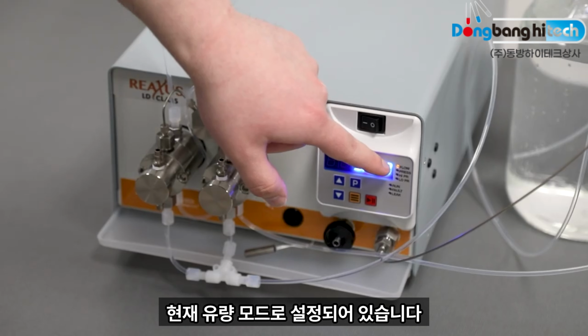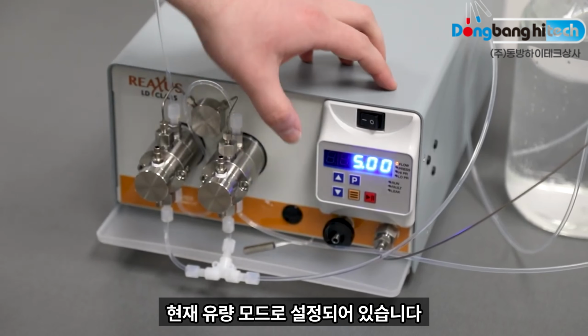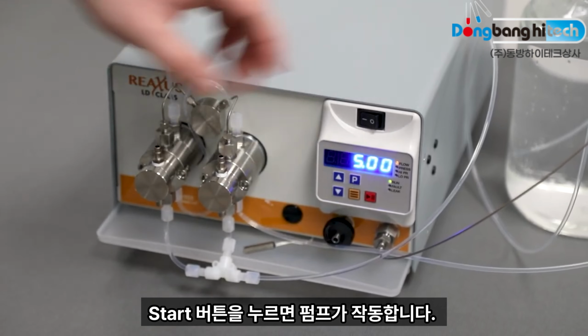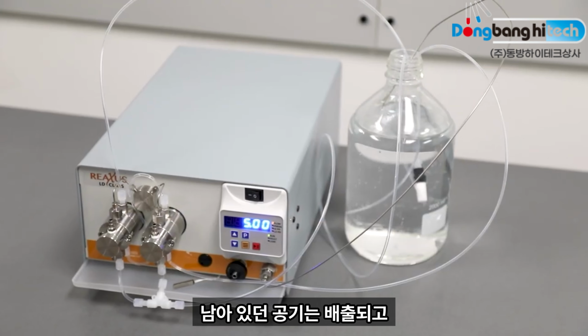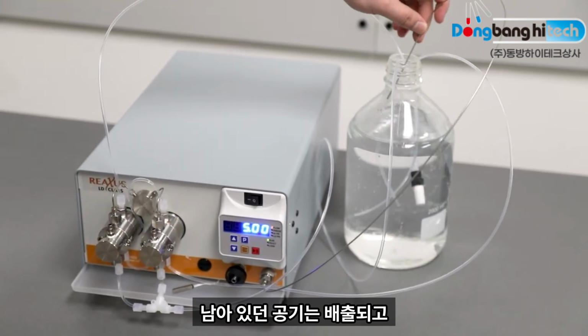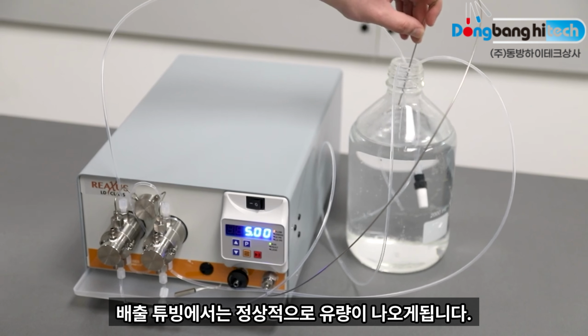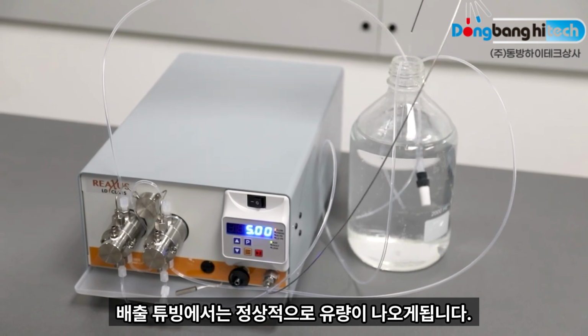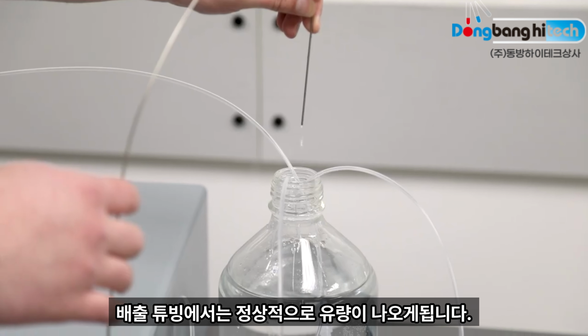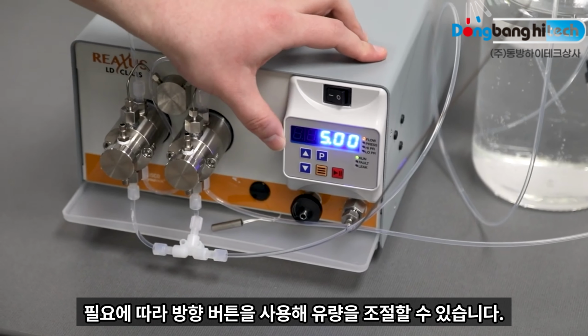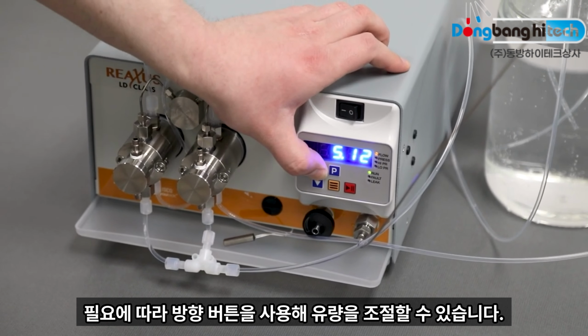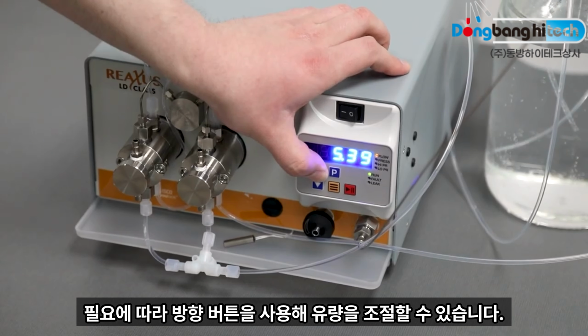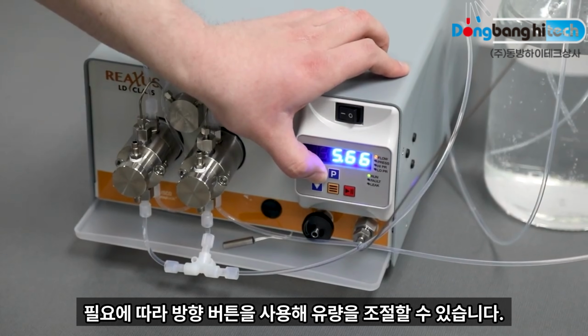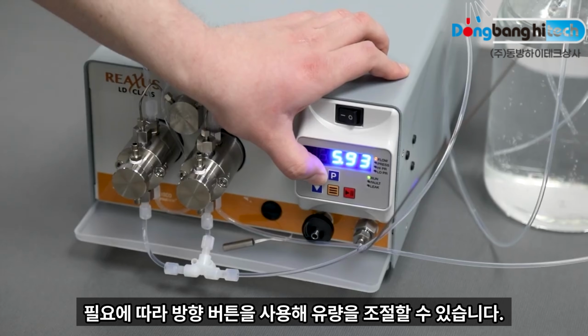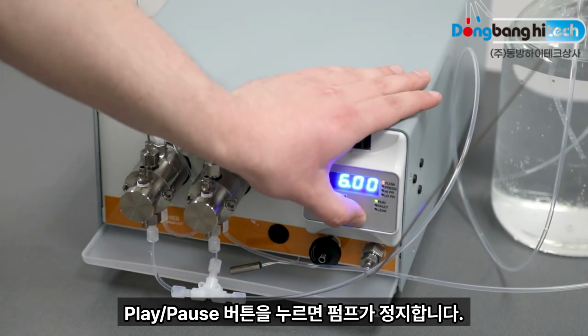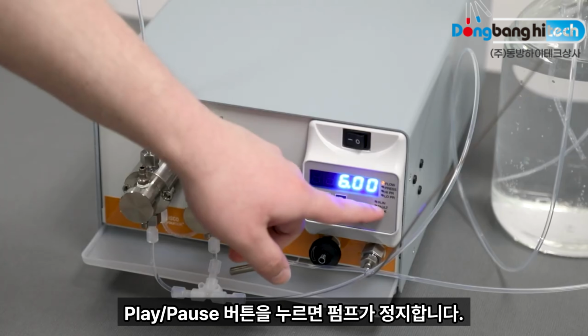Currently, I'm set to the flow position. If I were to hit start, the pump is now operating. Any residual air after the prime port will be coming out of the system, and I should be getting flow coming out of my outlet tubing. Depending on your application, you may need to increase the flow rate, which you can do with these directional arrows on your main keypad. To stop the pump, I can press the play pause button, and the pump is now stopped.